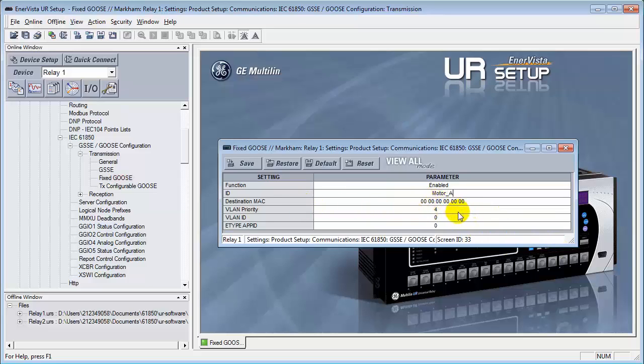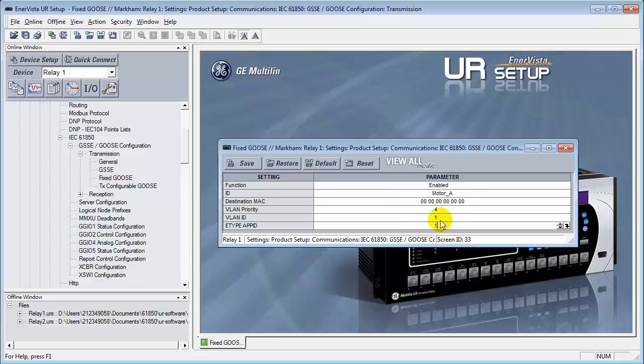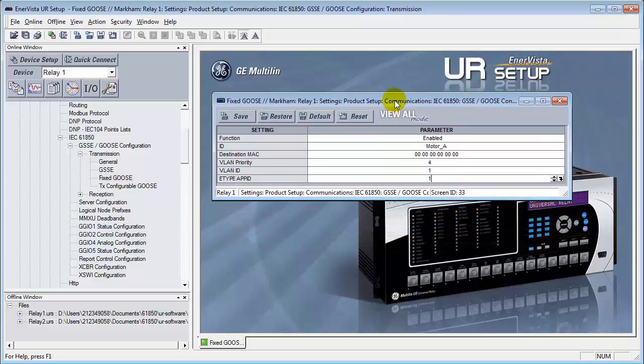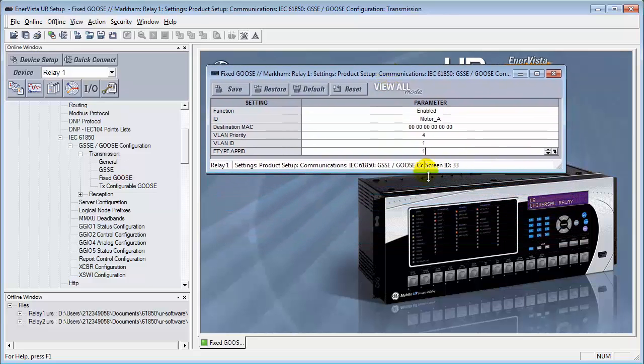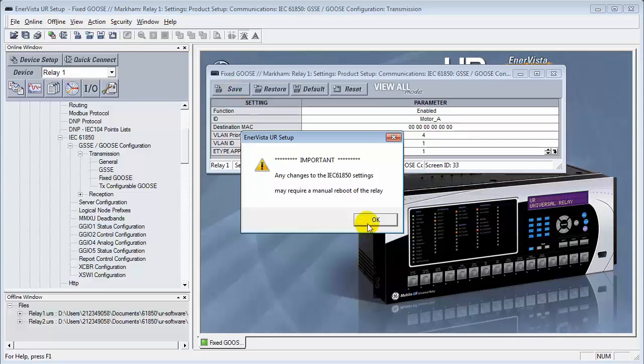We'll set up the VLAN priority with four. VLAN ID, let's put a one in here. And E-type application ID, a one. Now this can be whatever you want. Just as long as you remember what the subscription side has to have the same information as well. So it's extremely important to keep in mind what this information is. Let's save this.